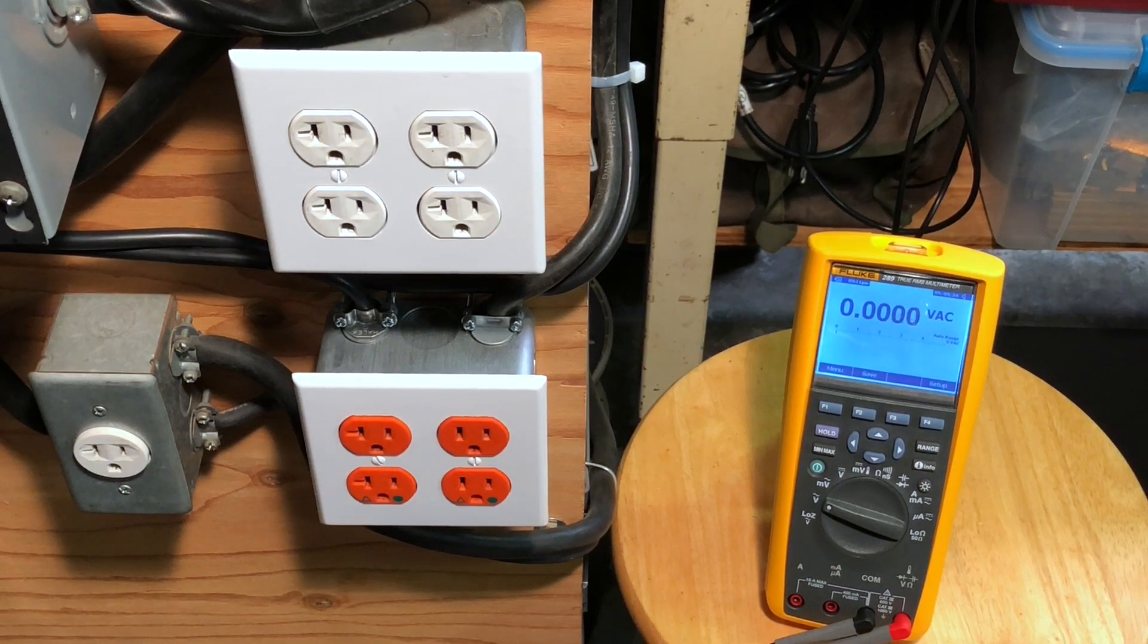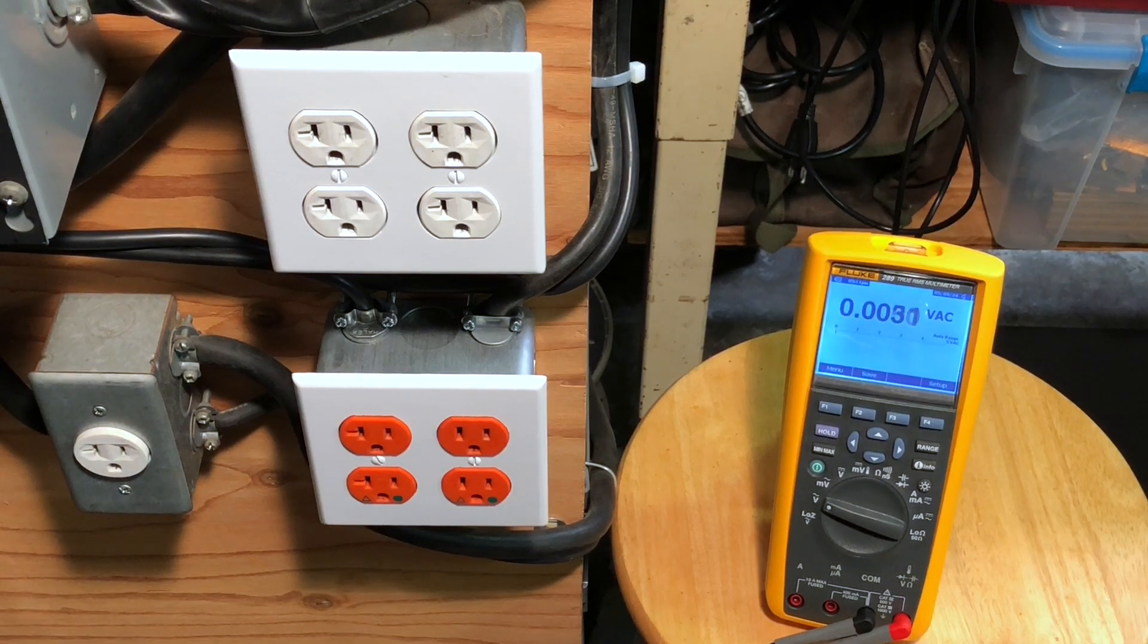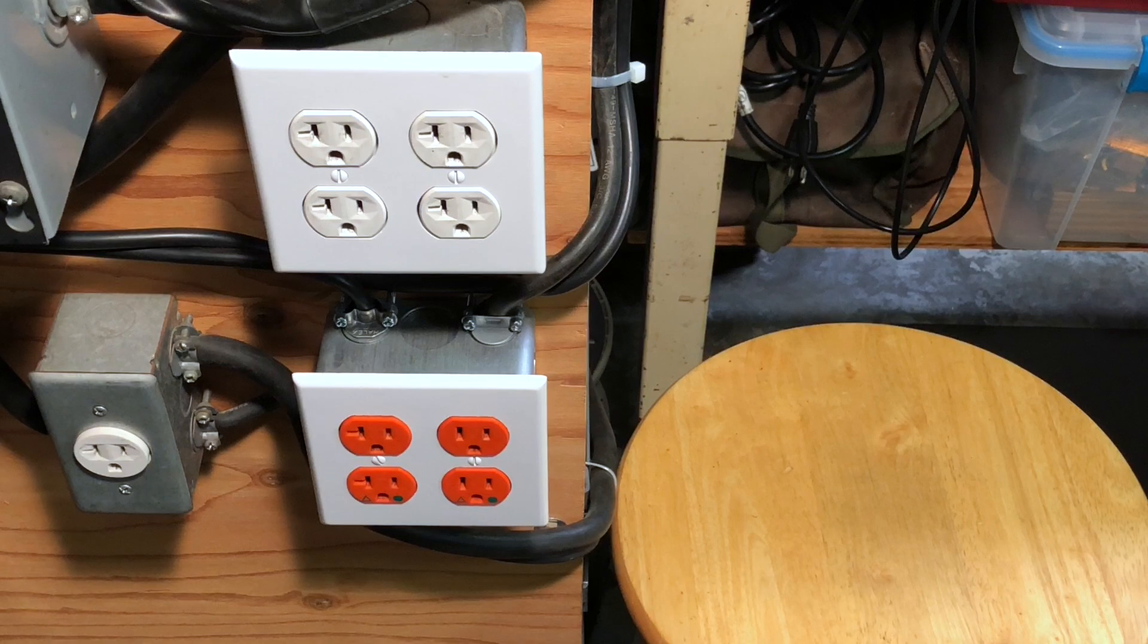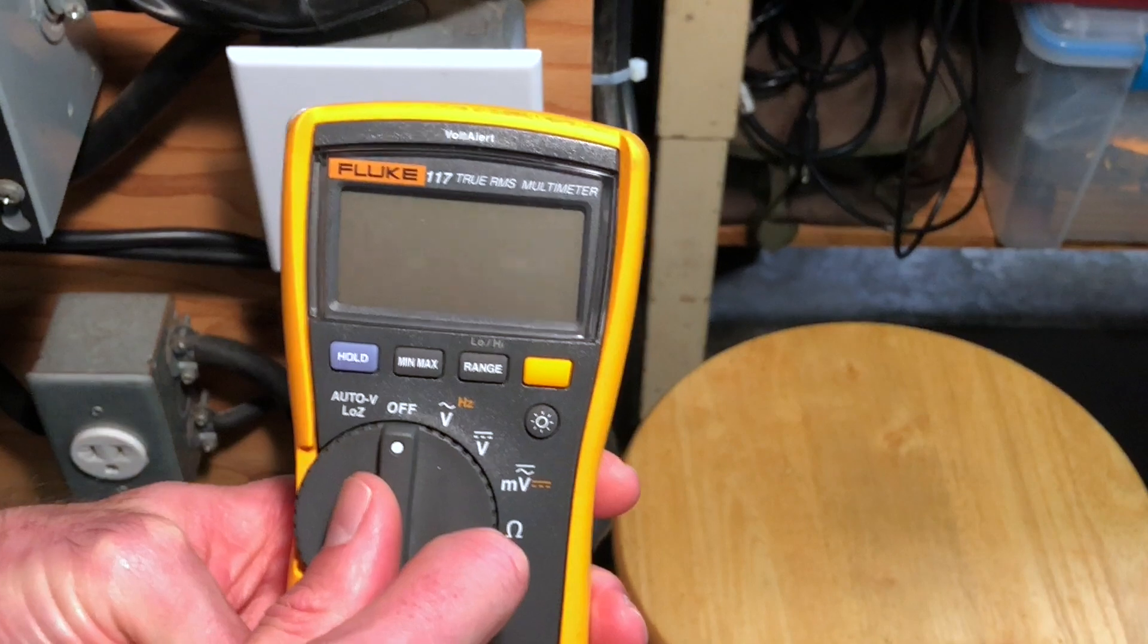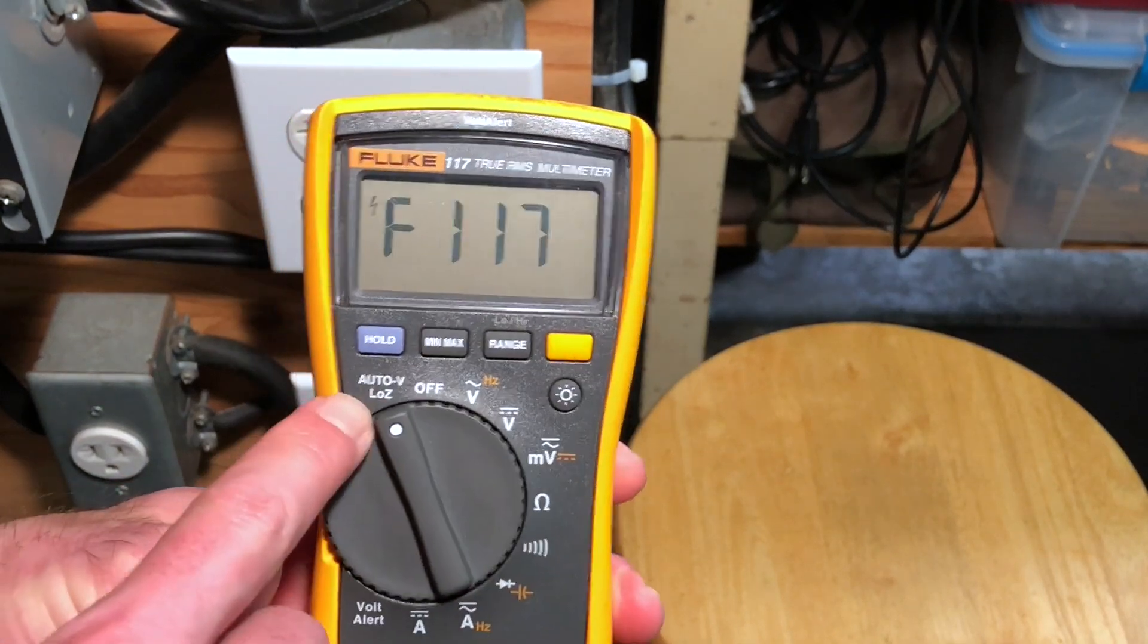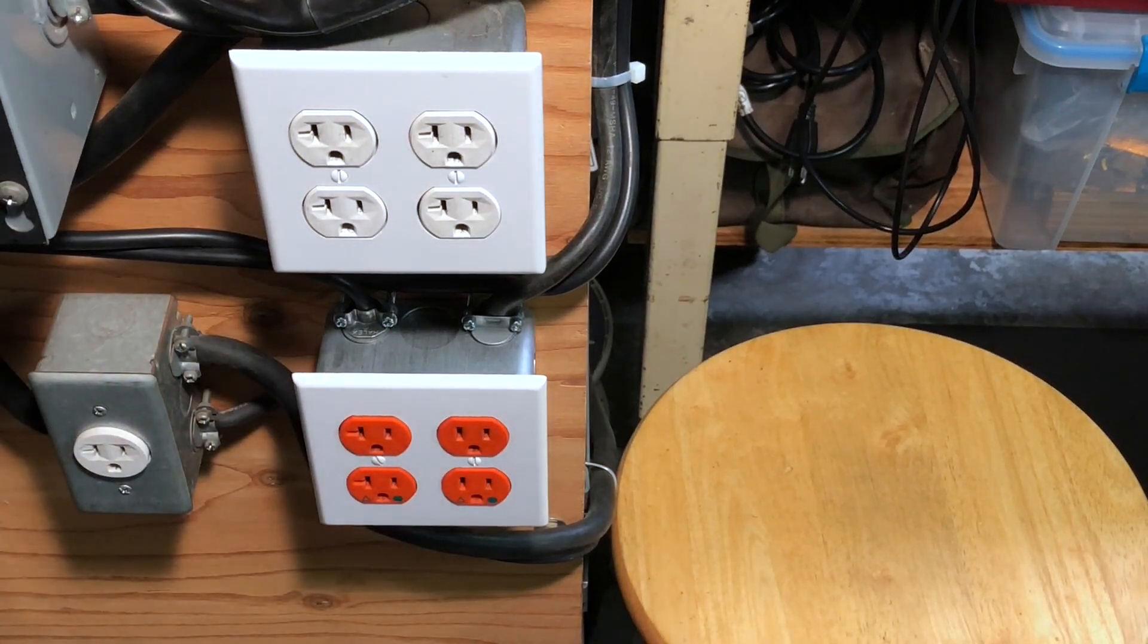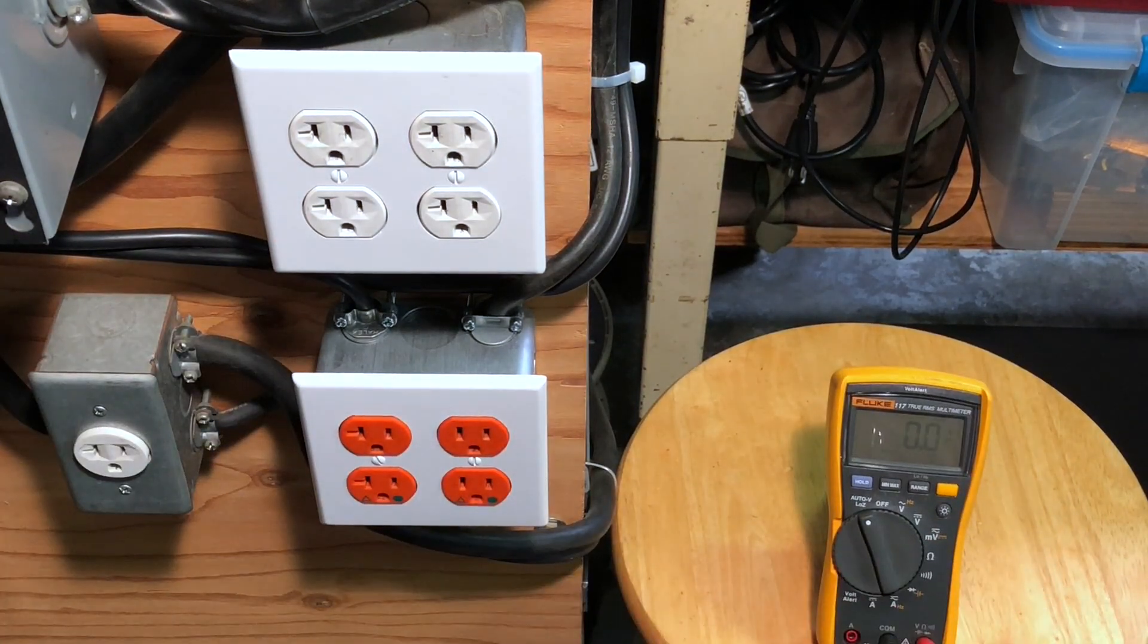When you're taking a reading for a ghost voltage and you get the readings like you just saw, you really should verify that with a second multimeter, just to verify there was no issue going on with the meter that you used and that the results were in fact accurate. Let me grab my other digital multimeter here.